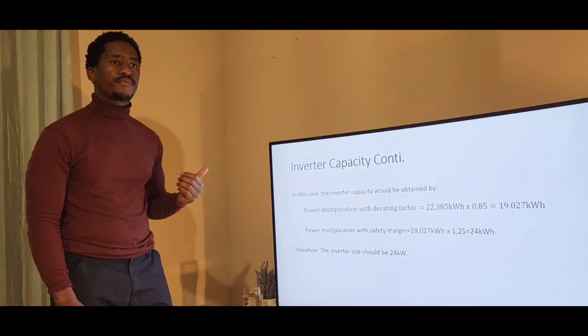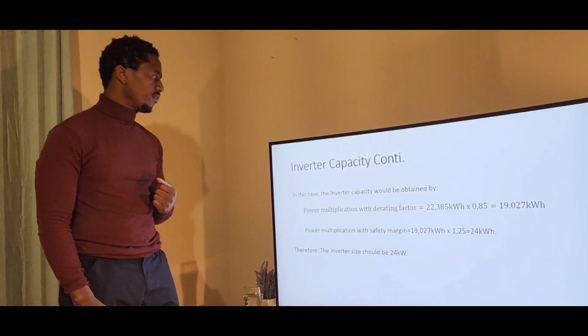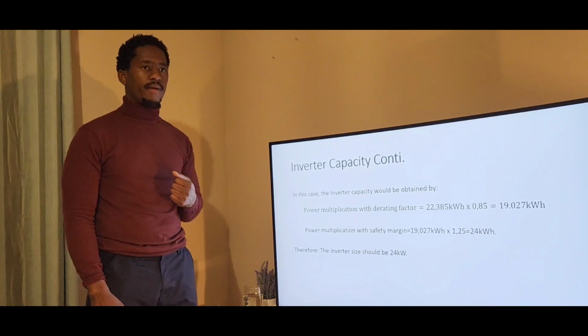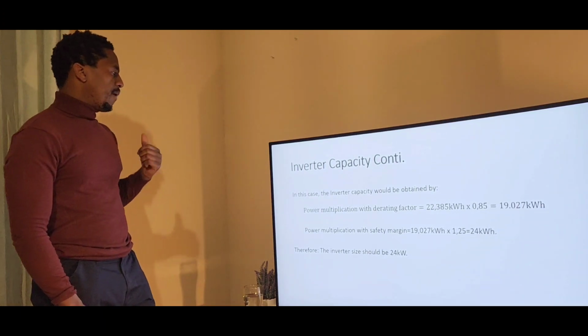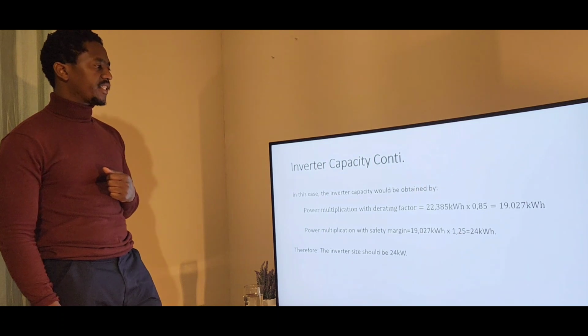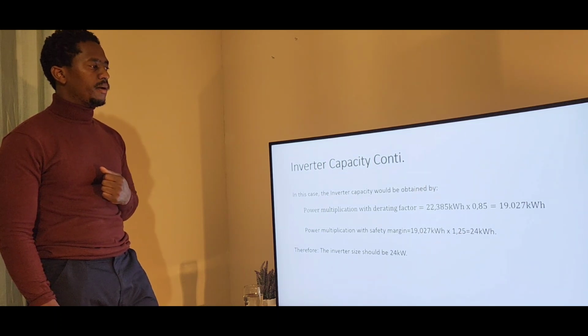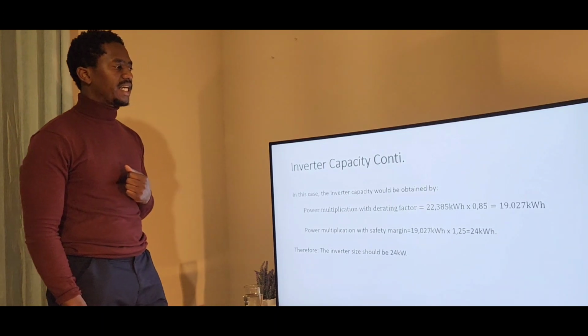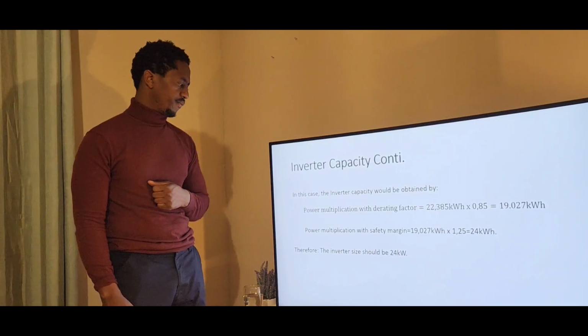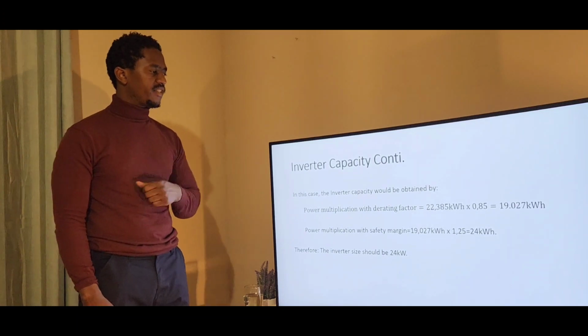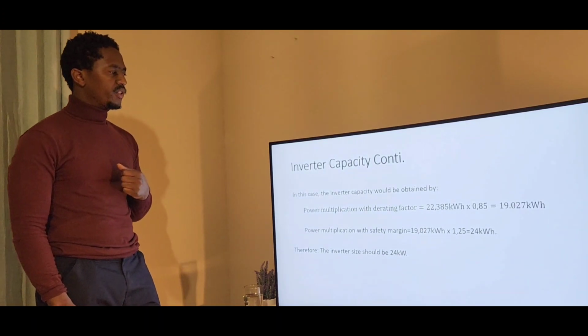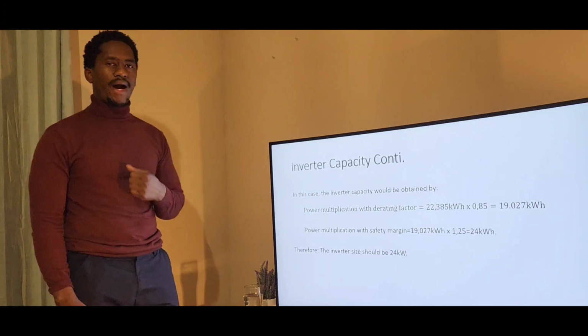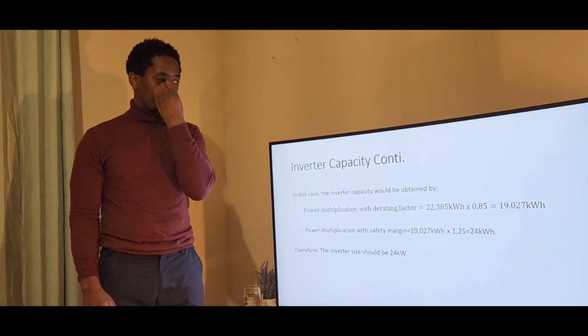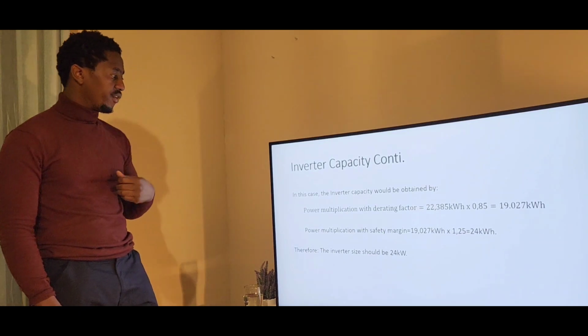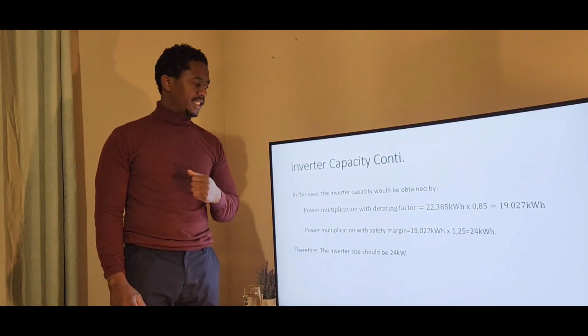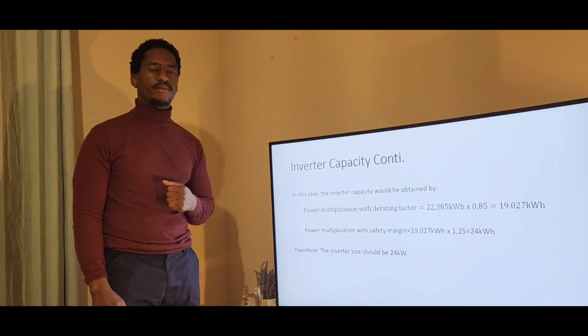In this case, the inverter capacity will be obtained by multiplying the power by the derating factor: 22.385 kilowatts by 0.85, which will give us 19.027 kilowatts. Then multiplying by the safety margin: 19.027 kilowatts by 1.25, which will give us an answer of 24 kilowatts. Therefore, the inverter size should be at least 24 kilowatts.